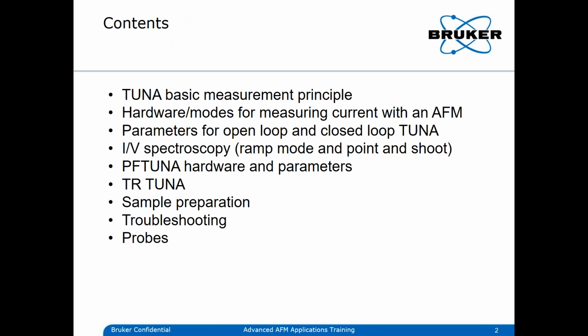So again, something about the basic measurement principle of the tunneling AFM, the hardware and the modes for measuring current with an AFM, and then about the parameters for the open loop and closed loop TUNA measurements. I will also cover a bit of IV spectroscopy, so in the ramp mode and in the point and shoot mode. Something more about the Peak Force TUNA hardware and its parameters. A brief introduction to torsion TUNA to complete this set of current measurements. Then something about the sample preparation, troubleshooting, and the probes we can provide for TUNA measurements.